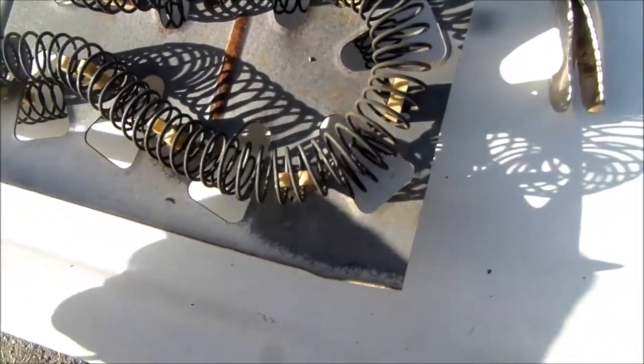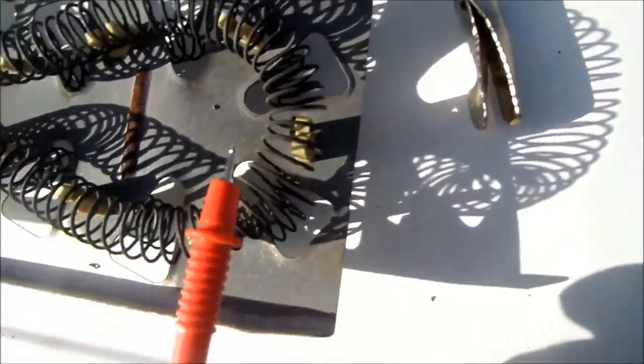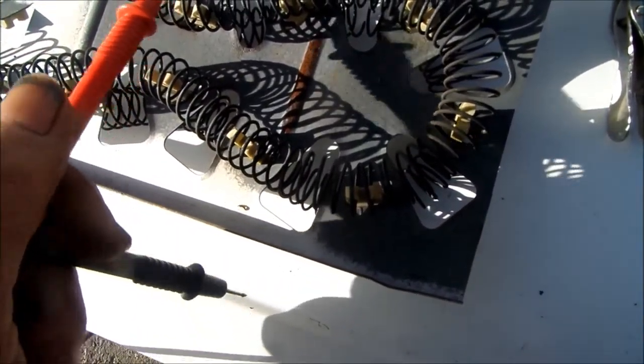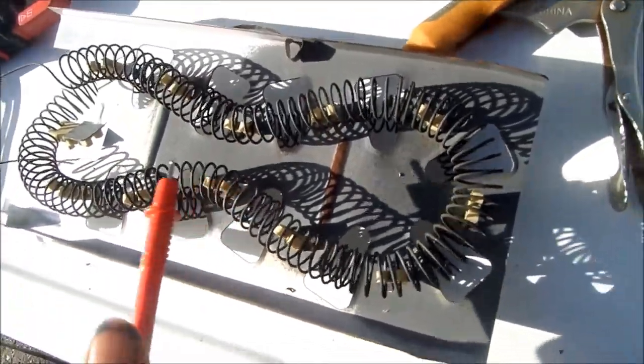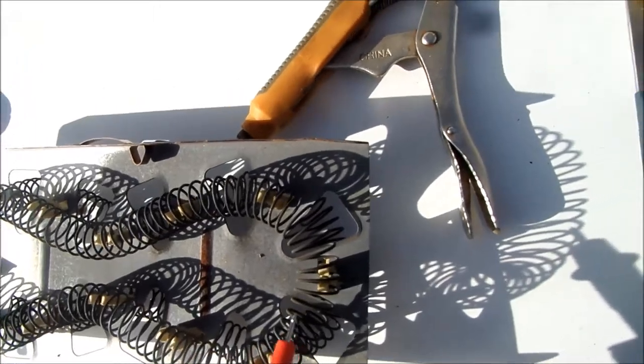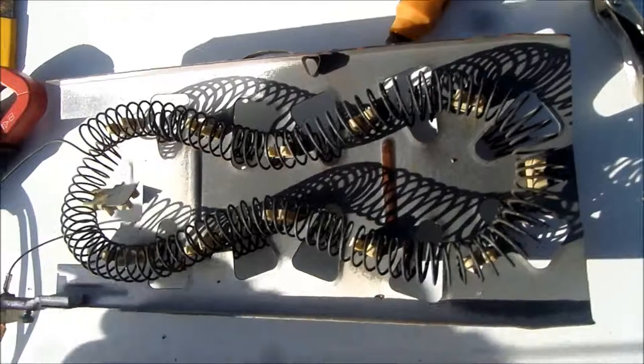And so if we take a close look at this heat element, it's best to try and not touch this heat element because oil on your hands can make one part of the heat element heat hotter than the other parts. So this one here, it's got a break in it somewhere.